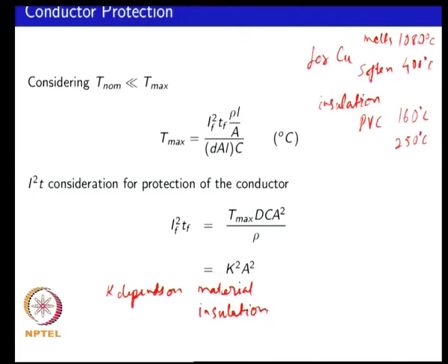ceramic. So, you will have to look at the surrounding materials, you will have to look at the configuration, whether this cable is sitting within a sheath, or whether there are multiple conductors, whether there is reinforcement within the cable. So, you will have to look at these factors to actually determine what is the level at which you need to protect the wire, and then select the appropriate protective device in an appropriate manner, or change the configuration in your design of what is the conductor that you would be using.